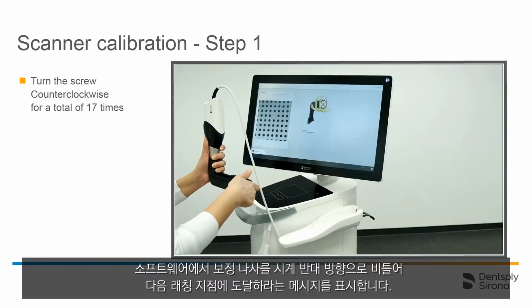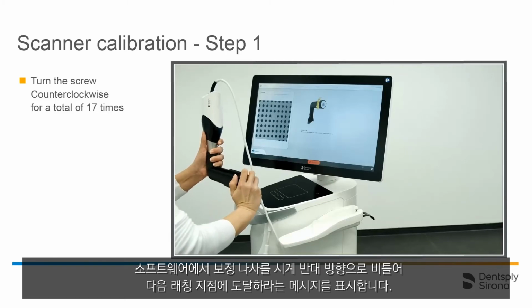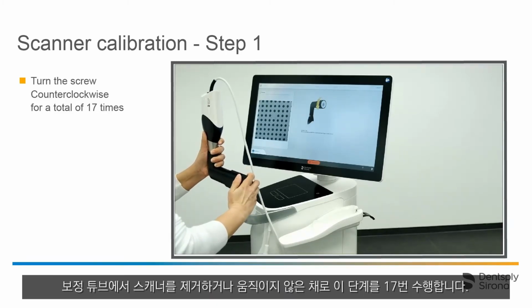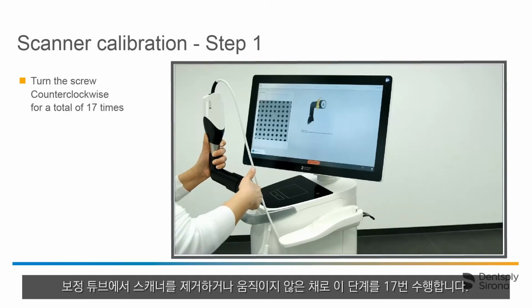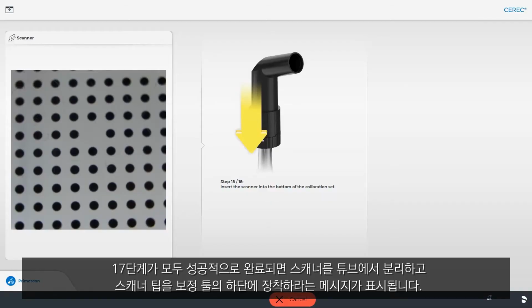Software automatically prompts you to turn the screw counterclockwise until you reach the next latching point. Perform this step 17 times without removing the scanner from the calibration set or moving it inside the tube. Once all 17 steps have been successfully completed, the software will prompt you to remove the tube and to mount the bottom side of the calibration set to the tip of the scanner.